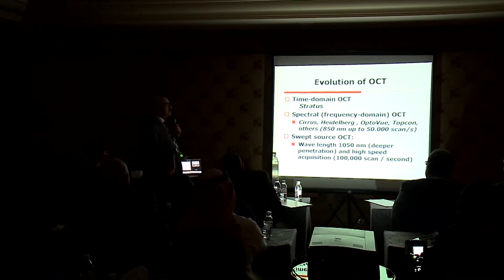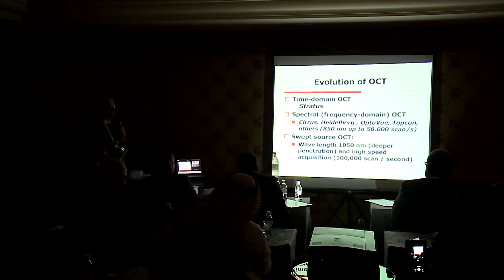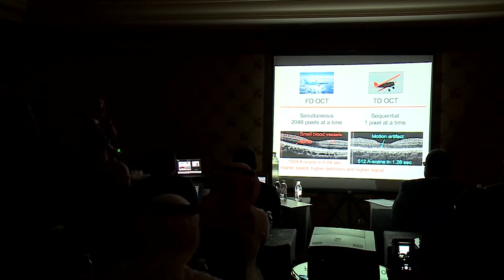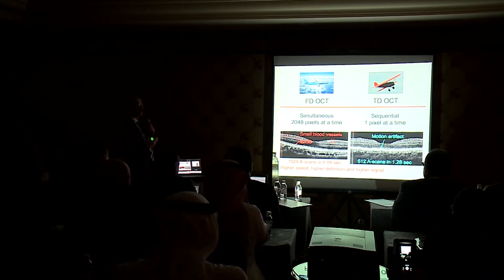We all know that there was evolution in OCT. We started with the time domain, then we went to the spectral domain, and recently we have the swept source with fast and deep penetration through the retina. Comparing old machines with new machines, we can see the acquisition time. We started at 512 A-scans in 1.28 seconds, then moved to 1,024 scans in 0.04 seconds, which gave us the ability to know the inner and outer retinal layers. We reduced artifacts and could interpret the OCT better.